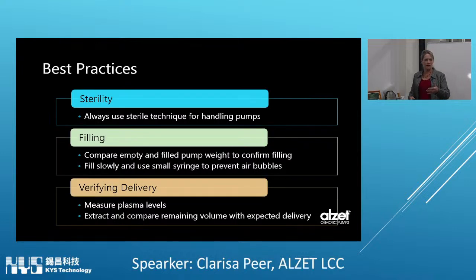The pumps come to you sterile inside the blister packaging, so we ask that you handle them in a sterile fashion as you're filling them and implanting them in the animal. When you are filling, we recommend that you compare the weight of the empty pump and the flow moderator together with the filled pump and its flow moderator as a way to confirm that you have the pump completely filled, and that you fill slowly and use a small syringe to avoid introducing air bubbles into the pump. It is possible if you go quickly and introduce air that you get the pump just partly filled, and then as you try to continue, the solution comes out because there's an air bubble inside. So if you can go slowly and avoid introducing the air to begin with, that will make the filling process easier.